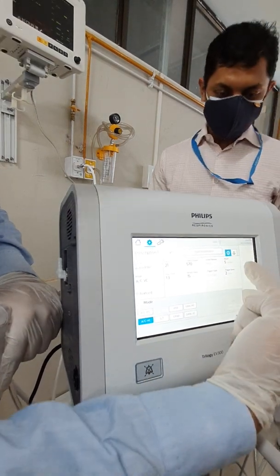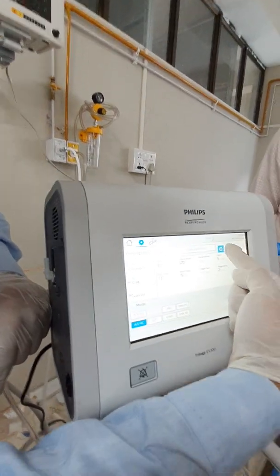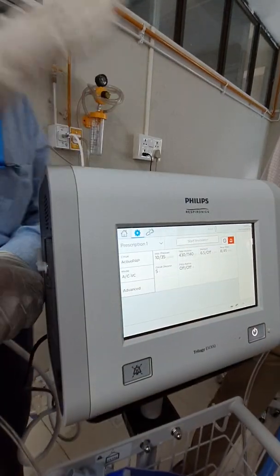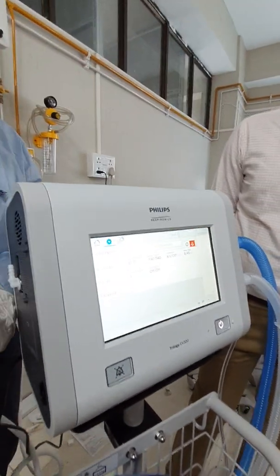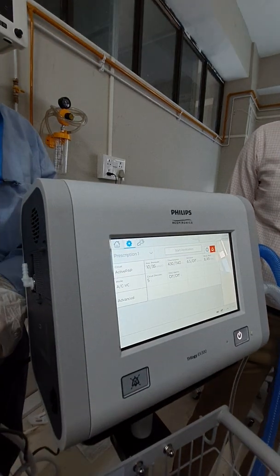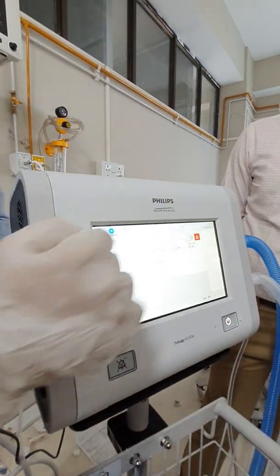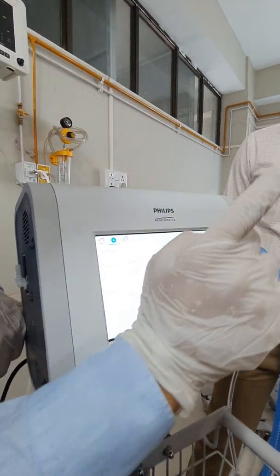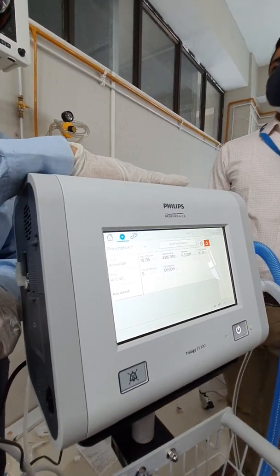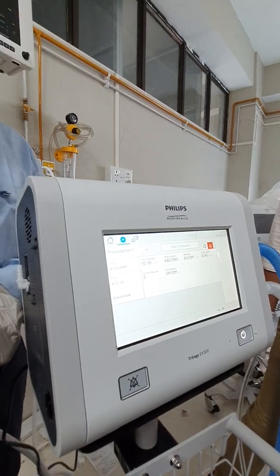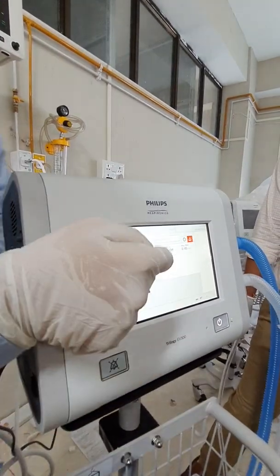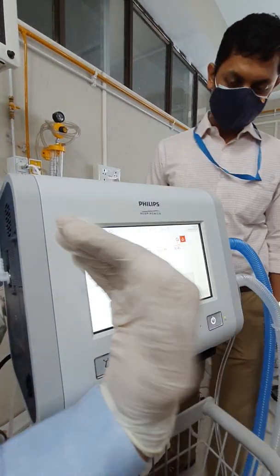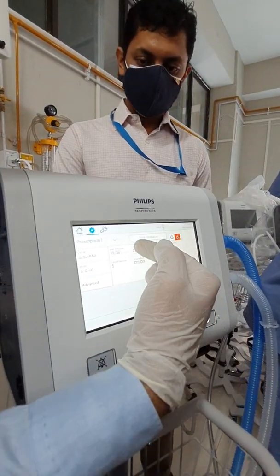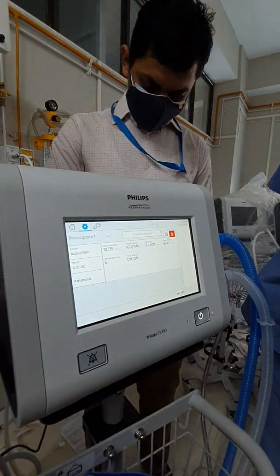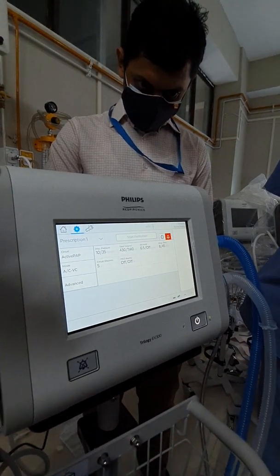Now, please remember one thing. There is one bell icon here. So this is the alarm settings. We usually avoid this. We just set it and go away. But in every training, I try to tell everybody, please check this. At least it will take 30 seconds. Because a patient of COPD and a patient of ARDS will have different alarm limits. Now suppose here what you see, 430 is the lower limit, and by chance if it comes down to 430, you will get an alarm.